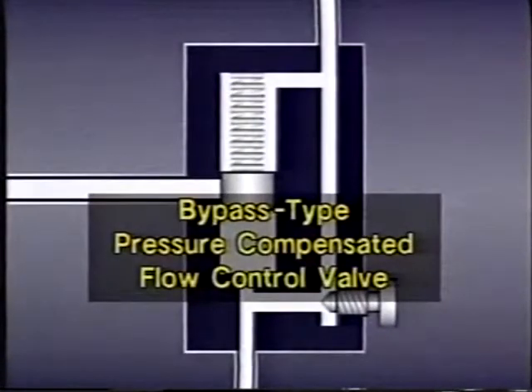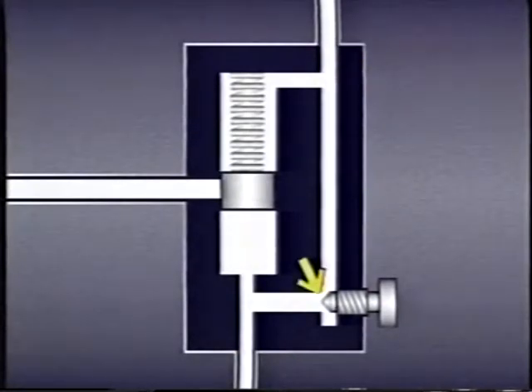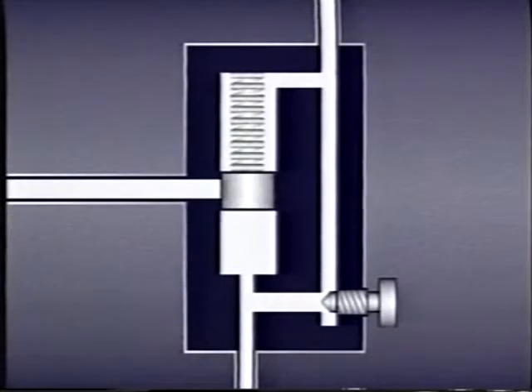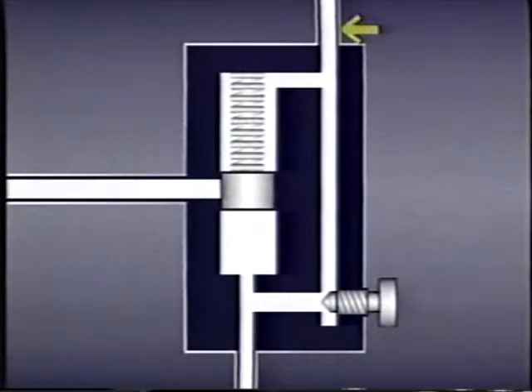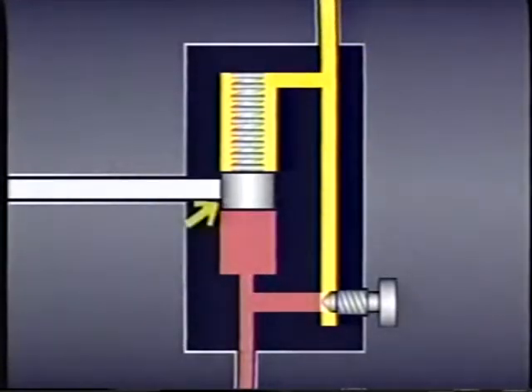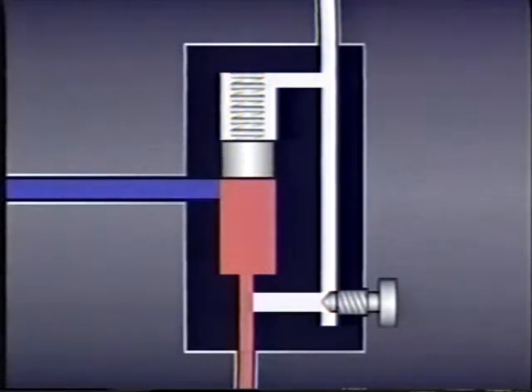Now let's look at the other type of pressure compensated flow control valve: the bypass type. Like the restrictor type, it has a valve body, an inlet and outlet port, a needle valve orifice, a compensator spool, and a spring to bias the spool. However, instead of two pilot passages to compensate for changing pressures, it has one pilot passage and a port to tank. The port to tank compensates for changes in pressure upstream of the valve, while the pilot passage compensates for changes in pressure downstream of the valve. In this type of valve, the compensator spool blocks flow out the tank port until pressure rises high enough to overcome the combined pressures of the spring and the pilot pressure downstream of the needle valve orifice. When that happens, the spool moves and fluid bypasses the orifice, dumping directly to tank.